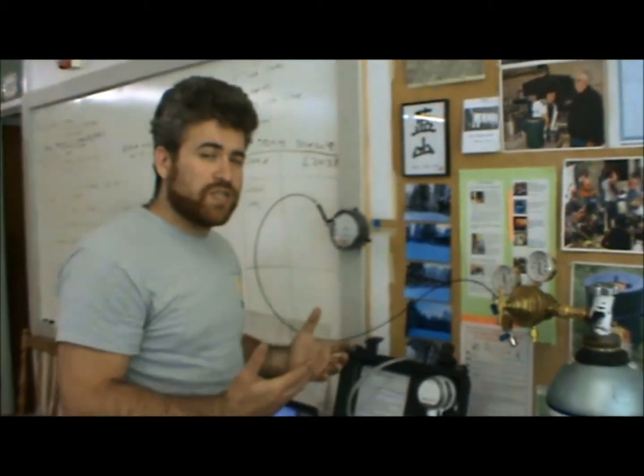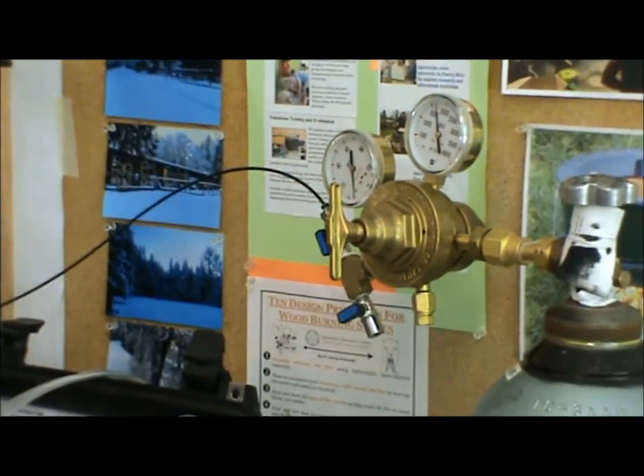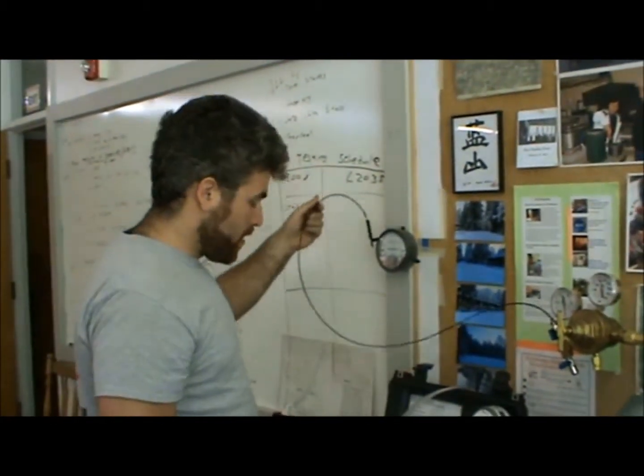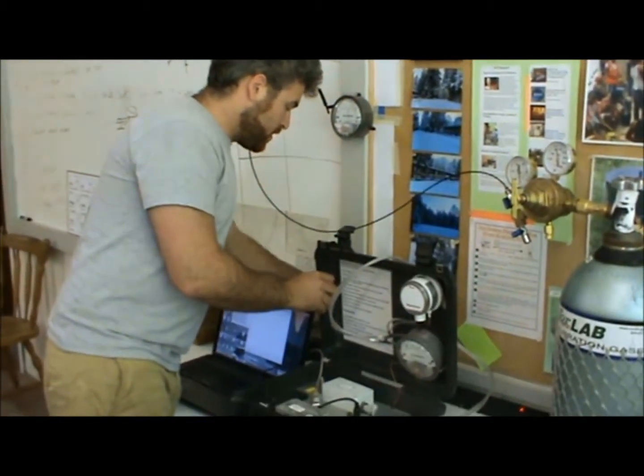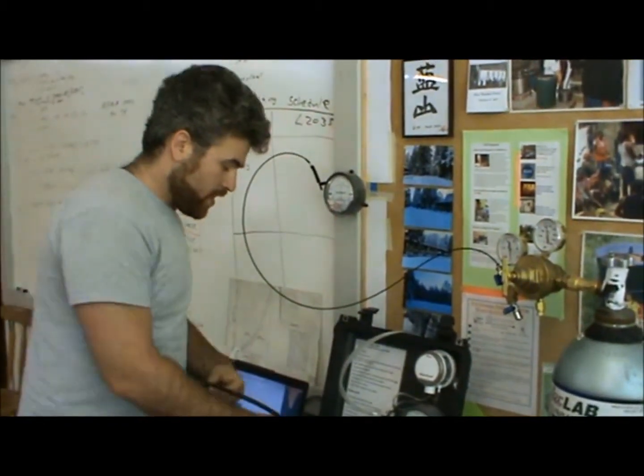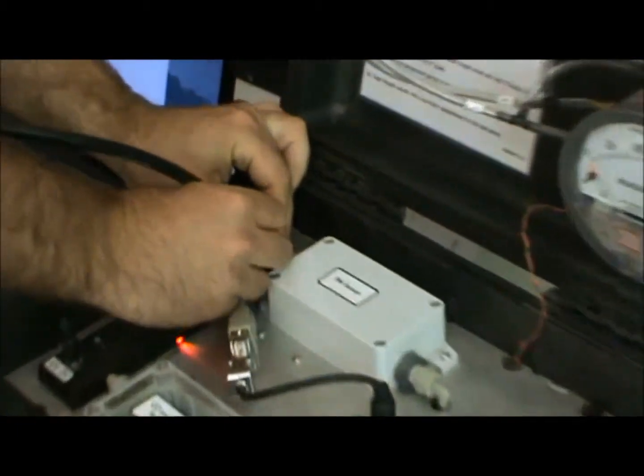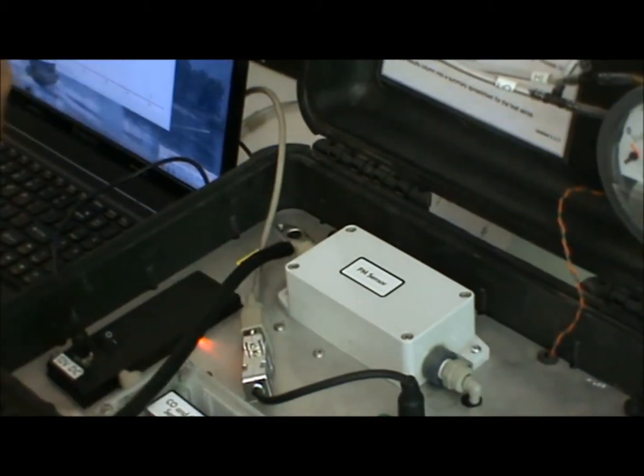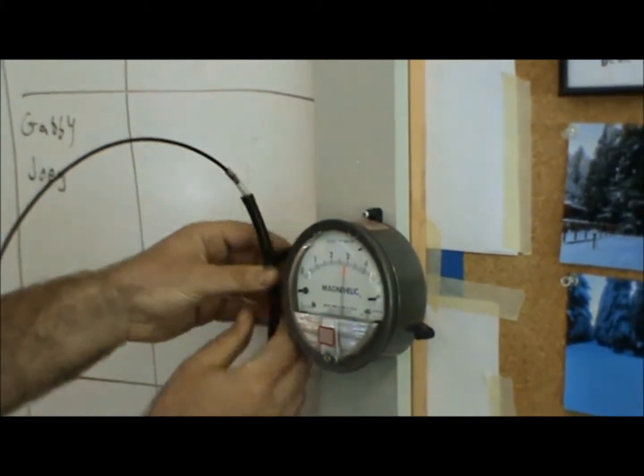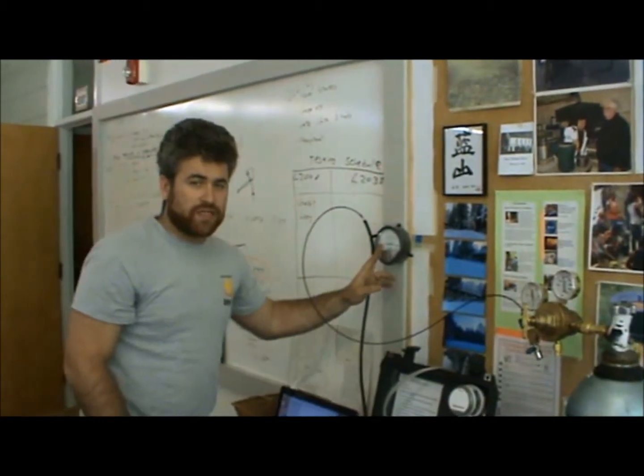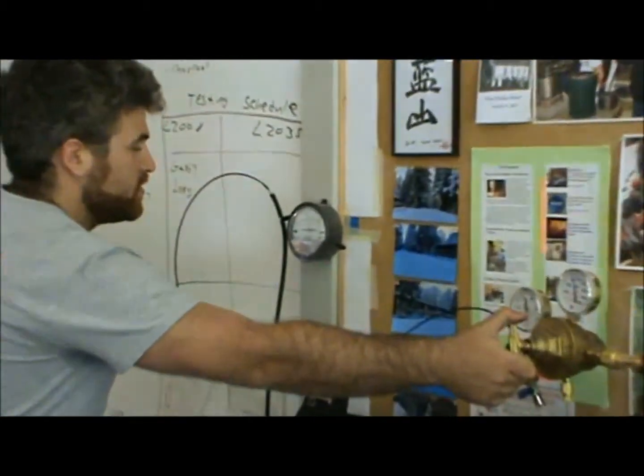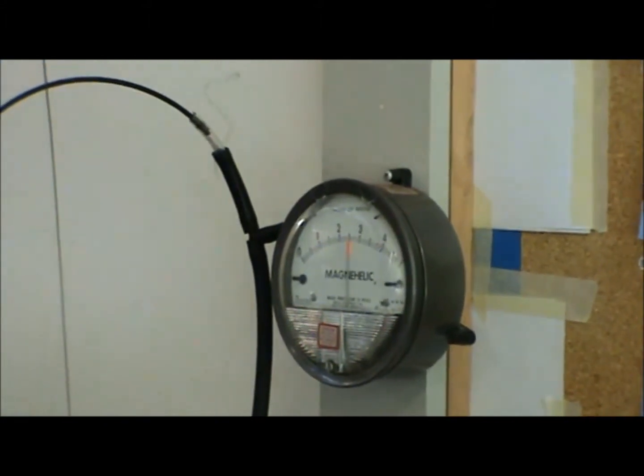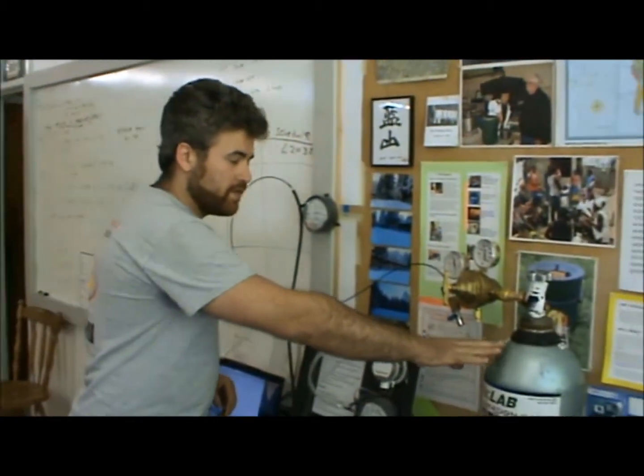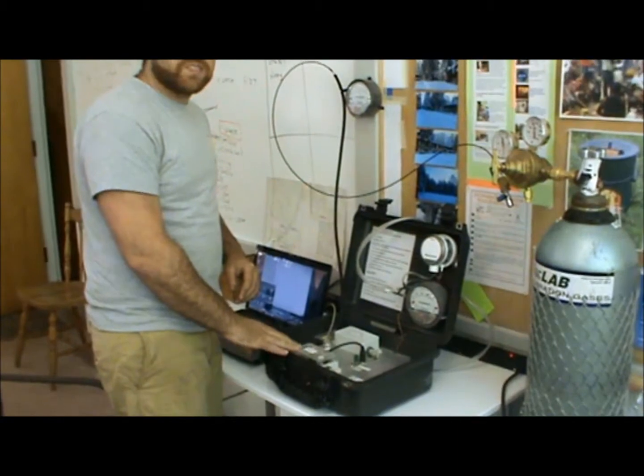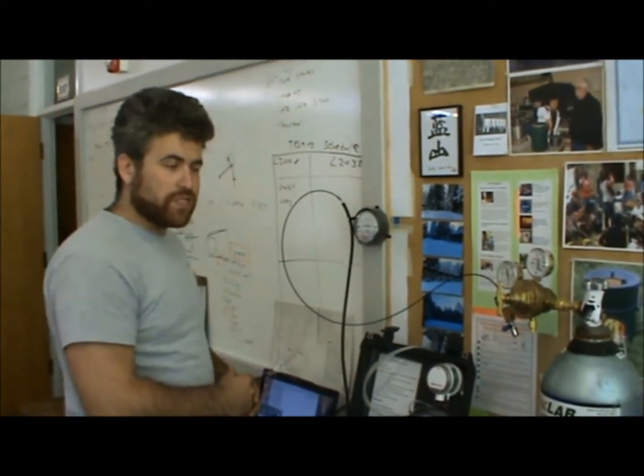Now, whenever I want to adjust how much gas is flowing, I can use this knob, which you'll see me do in just a second. I have it flowing through my magnehelic, and now we're going to connect my sensor box into that magnehelic and get some gas flowing into the sensor box. So I connect one side of my tube. You can use the same tube that is part of your LEMS or PEMS system. We take the other side of the tube and connect it into the magnehelic gauge. So now you can see my needle is not straight up, so I can adjust the gas tank until my needle is straight up. And that means that the pressure from the tank and the pressure of how far the sensor box is sucking is balanced. And that's what I want for this calibration.